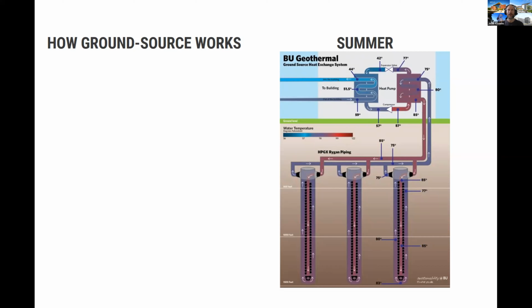In summertime, shown here in purple, we're rejecting heat into the ground, warming it up. We might send water down at 85 degrees and it comes back at 75. Then we use an electrically driven heat pump, basically a chiller, to pull that heat out of the building, reject it into the loop, and cool the building.